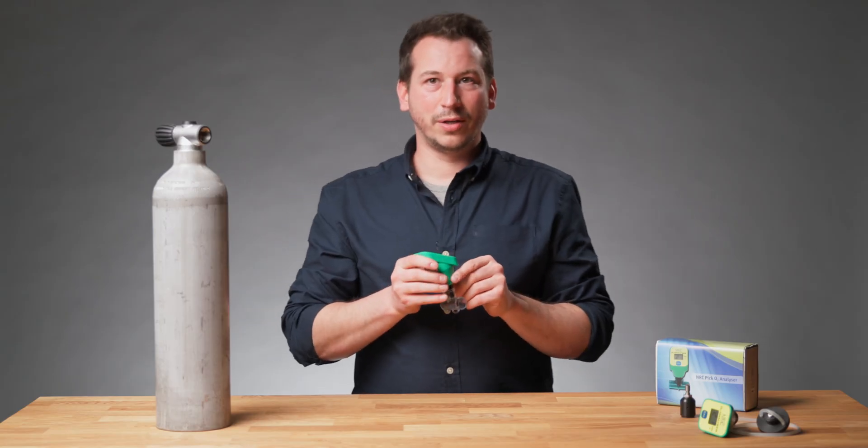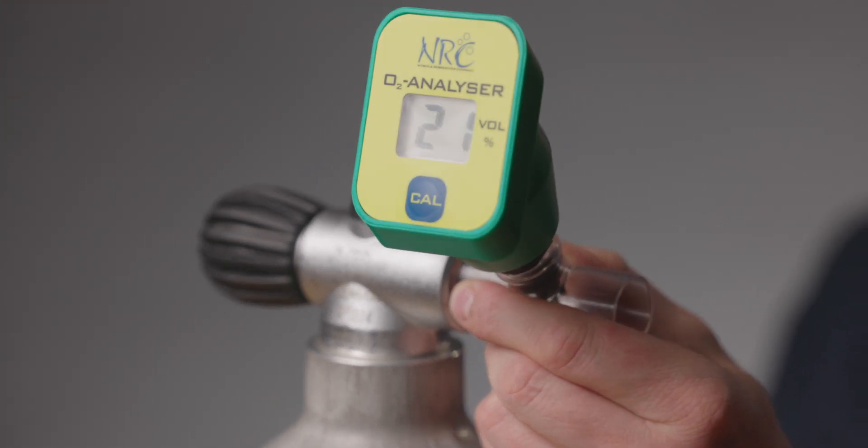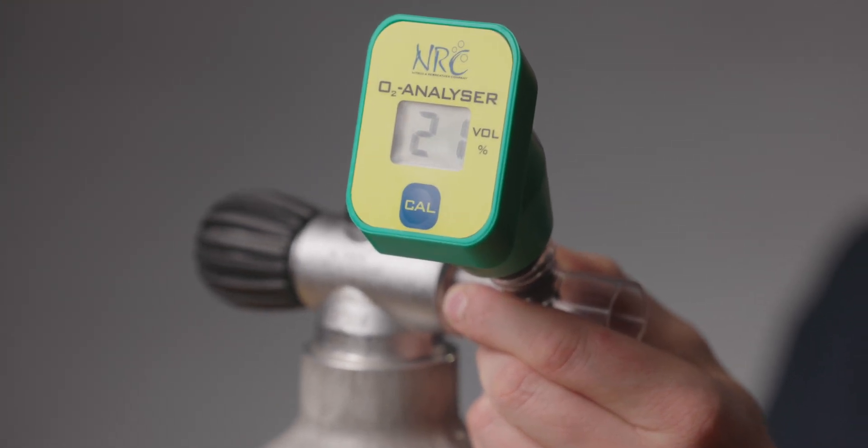If you are in a high humid environment, we recommend to calibrate the analyzer on a diving cylinder filled with air.